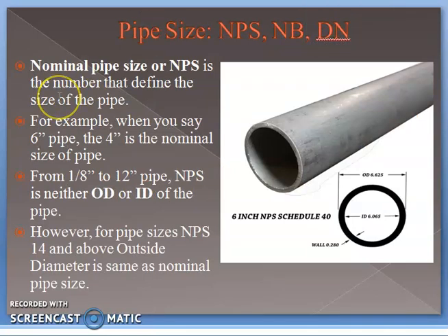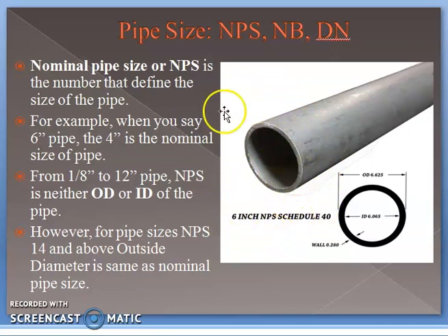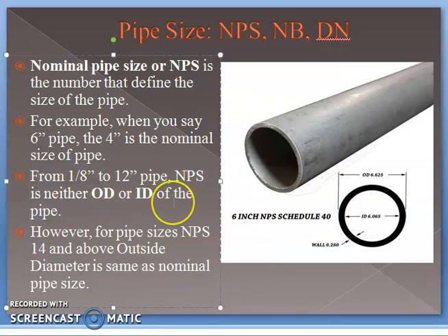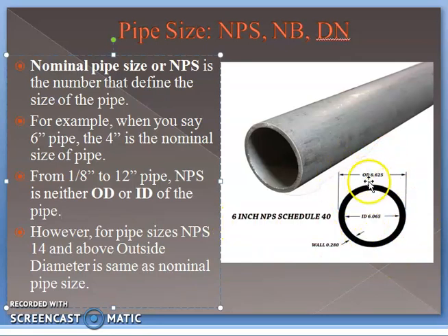NPS — Nominal Pipe Size — is a number that defines the size of a pipe. For example, consider a six-inch pipe with NPS 6 and Schedule 40. In the NPS system, from 1/8 inch to 12 inch, NPS is neither the OD nor the ID of the pipe. For a 6-inch NPS pipe, the NPS is 6, whereas the outside diameter is 6.625 inches and the inside diameter is 6.065 inches.